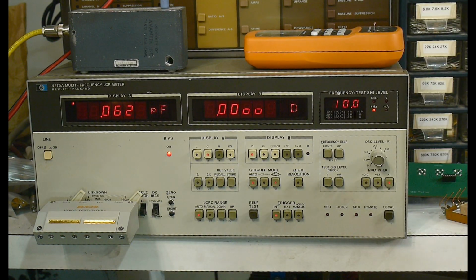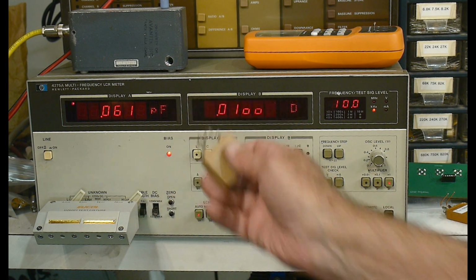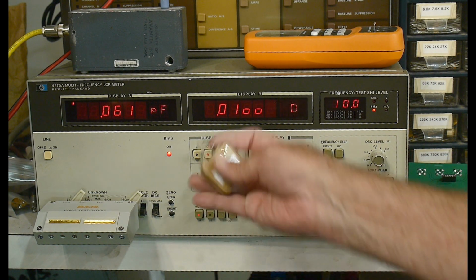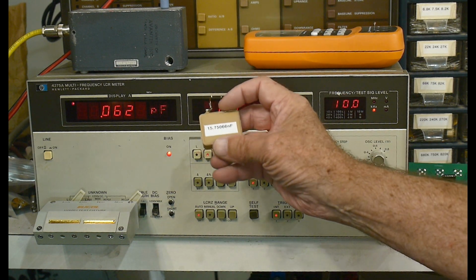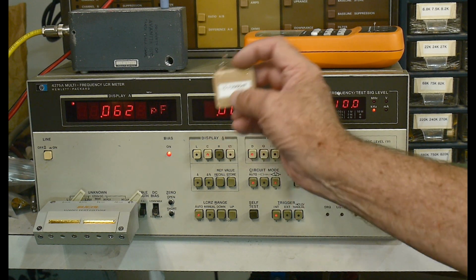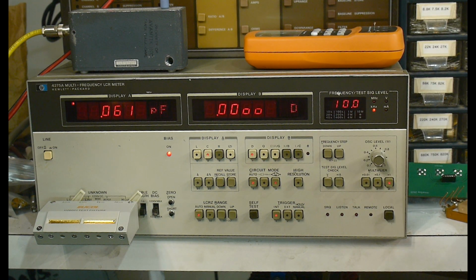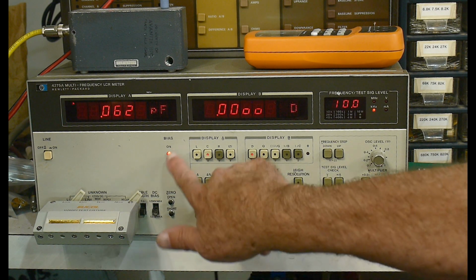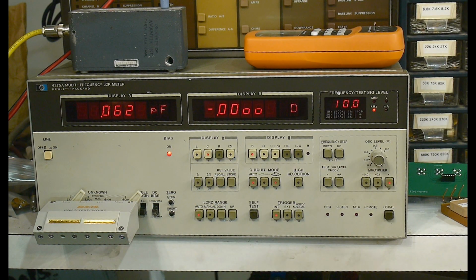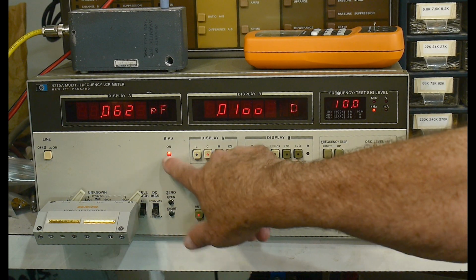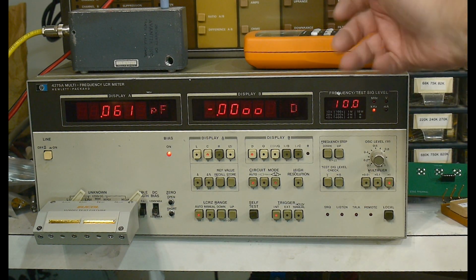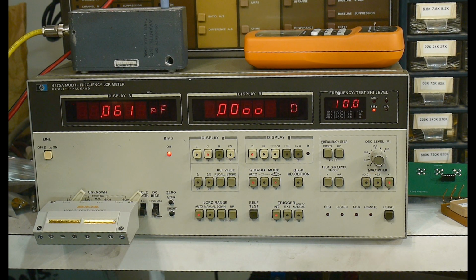So I've measured a whole bunch of things that I now know as secondary standards. And I already had some capacitors that were 0.3%. So I can use those. Plus, I've made a secondary standard out of these. So this is the number measured on the Keysight instrument. So I've labeled all of the stable capacitors I have to use as secondary standards. So anyway, like I beat that into the ground. Let's see, I don't need bias anymore. I need to turn that off in the back. It's set to 0. Even though it says bias here, it's set to 0 in the back. You need to turn a lever in the back to turn that off.